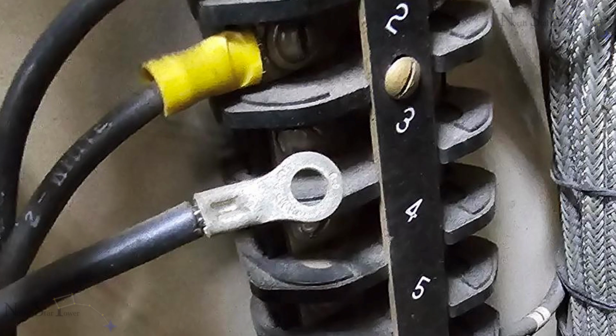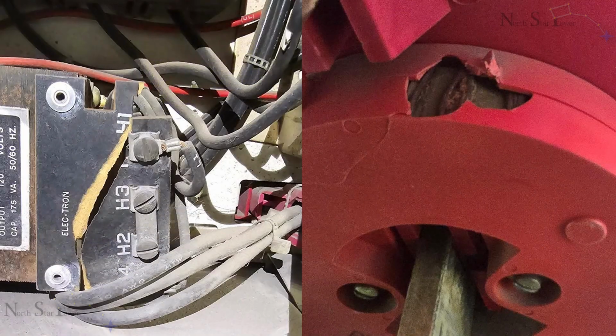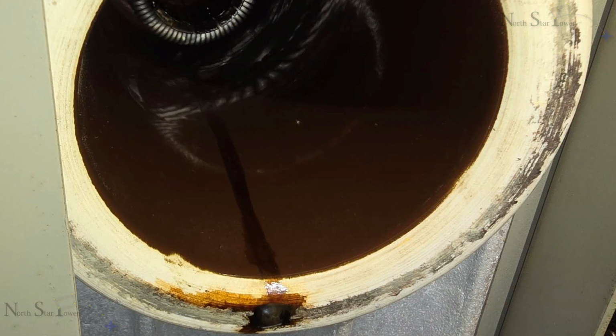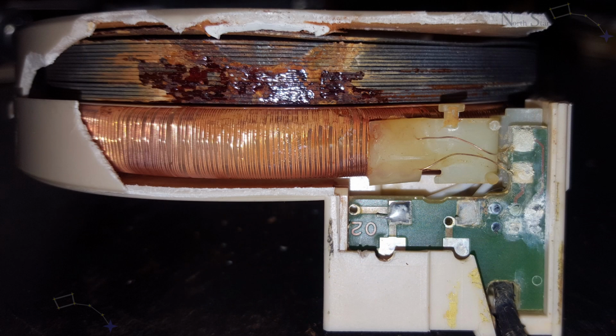You also want to check the substation and floor for debris coming from the substation components. Hardware that has fallen out, and signs of damage like dents, cracks, or paint scrapes. You also want to look for visual signs of arcing or flash damage, such as scorch marks and melted components.